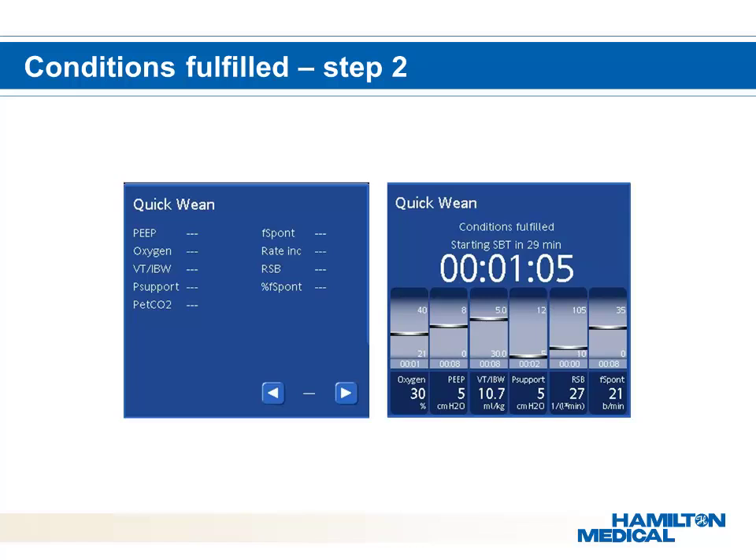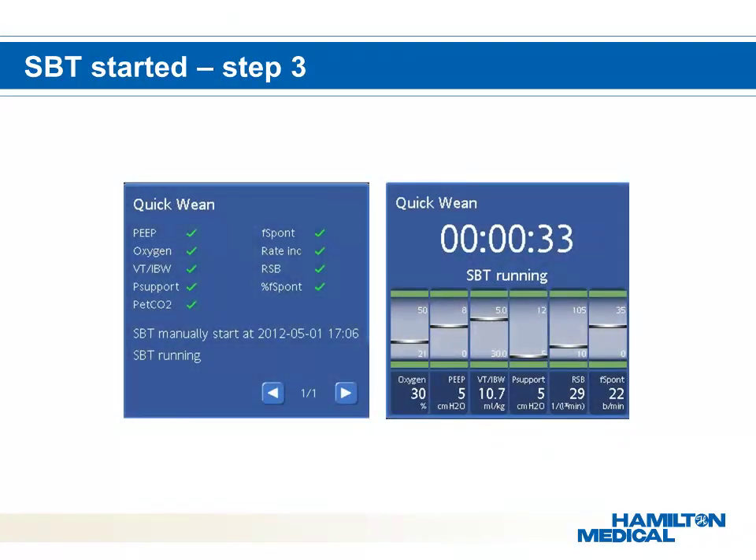The three stages of the quick wean functionality within INTELLiVENT-ASV are graphically displayed differently to highlight the different stages of ventilator support and make the caregiver graphically aware of active weaning of their patient. When the patient has met the conditions for a certain user-defined time, the last step will follow — called the SBT. Once the SBT has started, the percentage min vol is decreased to a default of 25%.